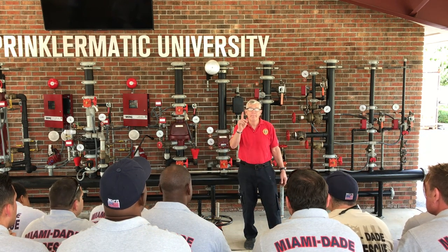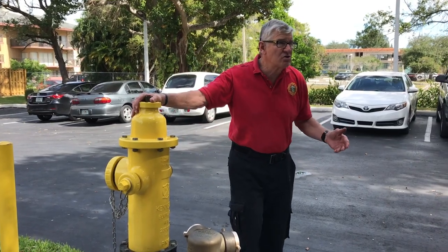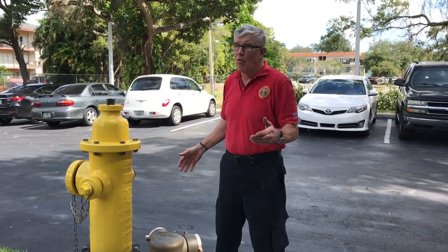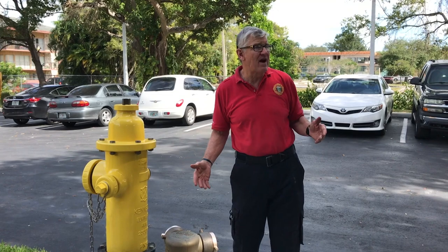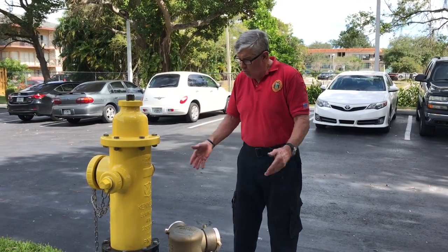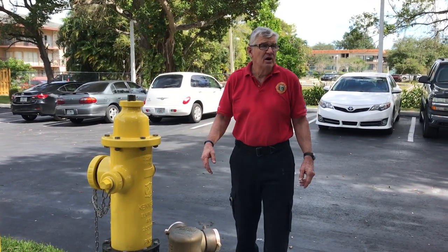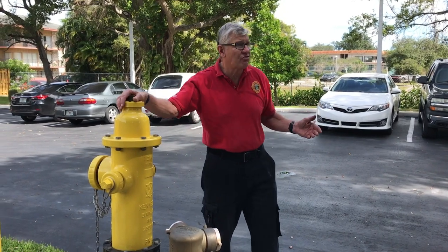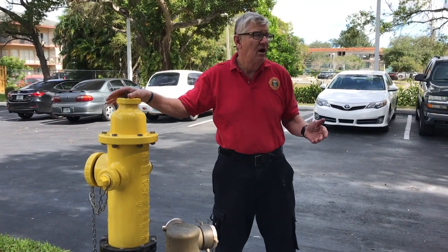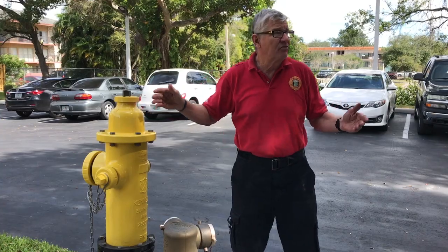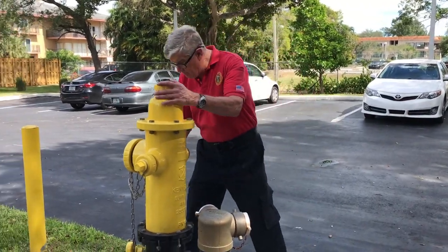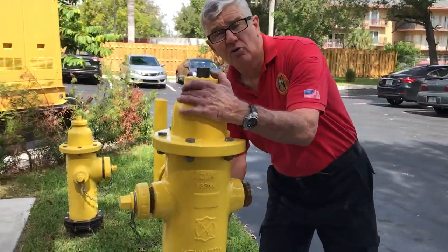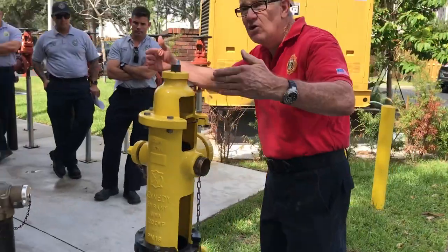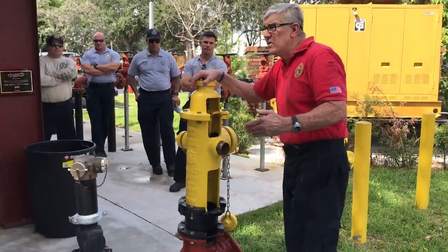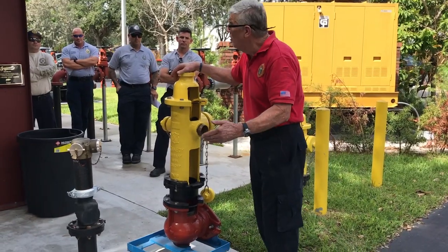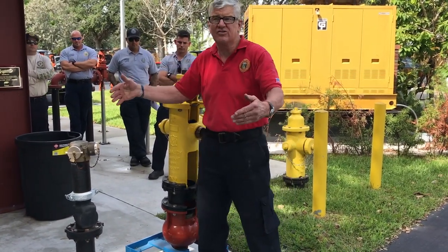Okay, AJ. Cool. The water. How does the water go from the city water main into a building fire suppression system? Water main, of course, is under the ground. Now, we live in South Florida, so we don't have freezing weather. In the northern climates, the inlet to this fire hydrant, which is connected to the water main, or at least a T off of the water main, would be a number of feet down below what we call the frost line.